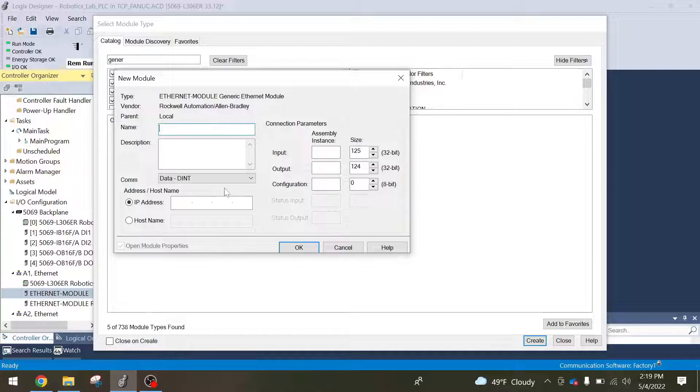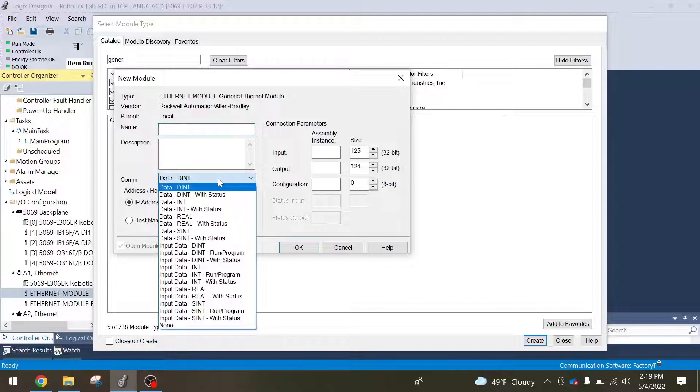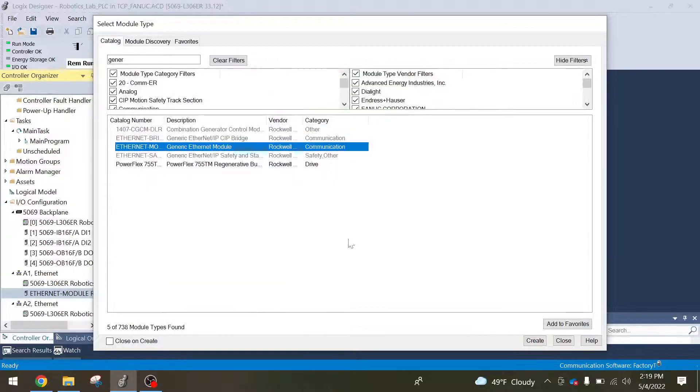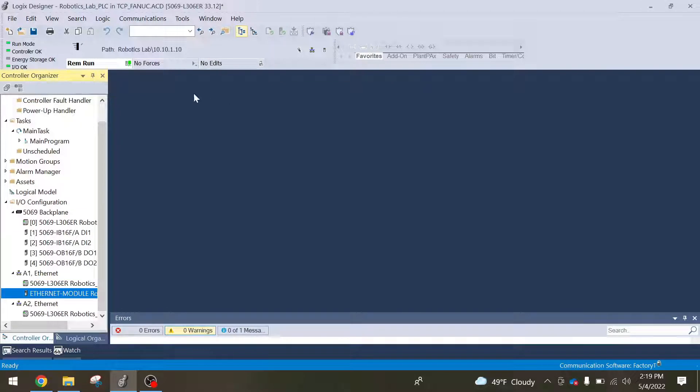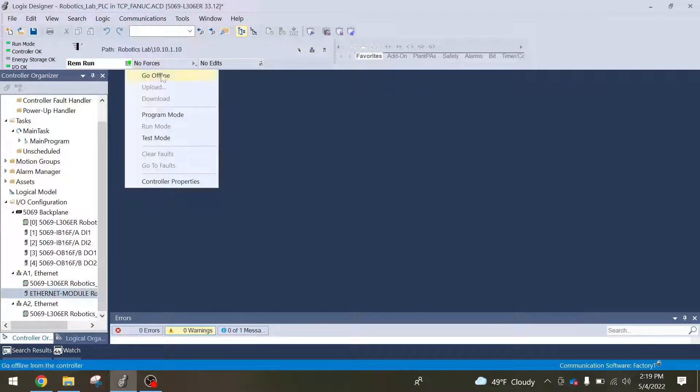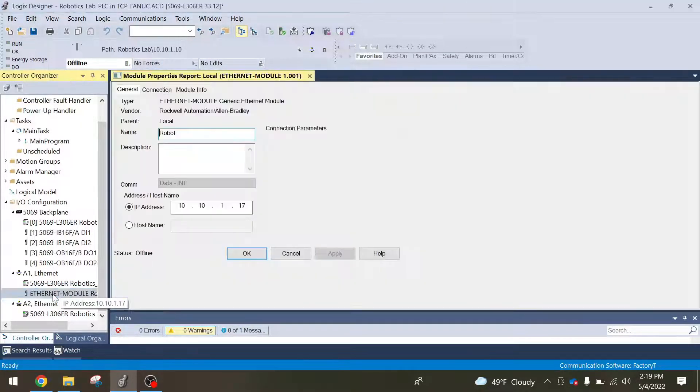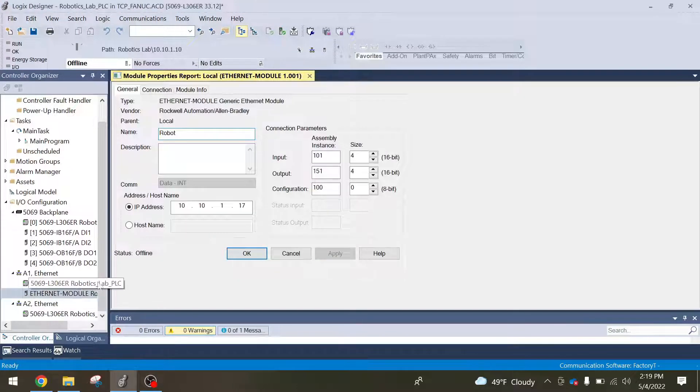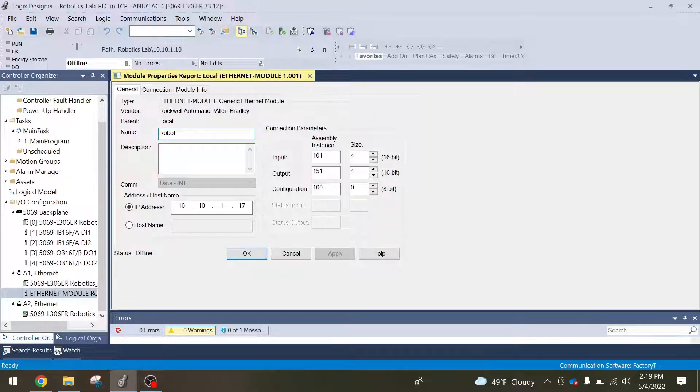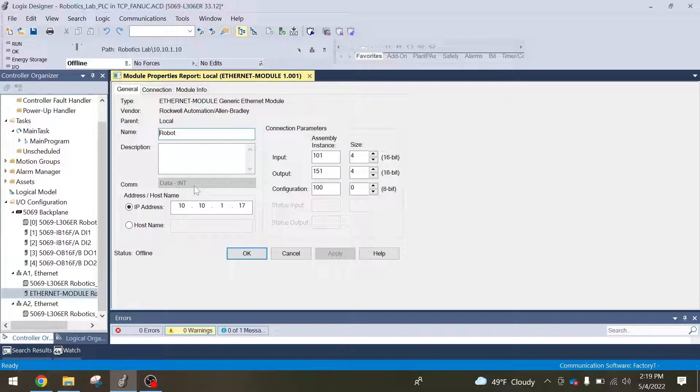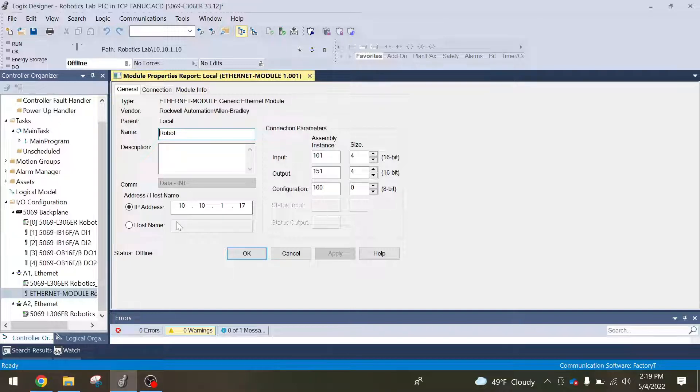First thing I want to point out here is this, it's going to default to data-DINT. You want to change that to data-INT. I'm going to cancel out of this just because I have a module already made with all the correct information in it. I'm going to give it robot names, mine's pretty generic. Again like I said before, data-INT. Then you're going to put in your IP address of the robot. Make sure your first three octets match that of your PC and of the PLC and then your identifier, that .17 is different from each of the other devices.